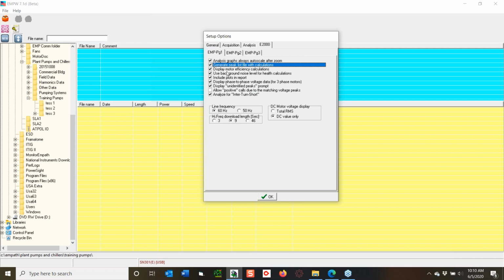The ones that are showing right now are positive, are the defaults. Display motor efficiency, use background, include plots and report. Display phase-to-phase voltage data for 3-phase motors, and then also display unidentified peaks prompt. What that does is identify bearings that you have not included. So primarily unidentified peaks means you've got some multiplier times RPM that's not an integer that shows up within the alarm settings you set. And then allow positive calls to that. You leave that unchecked to allow the potential of false positives. Personally, I prefer false positives because then I can go in and analyze it myself.